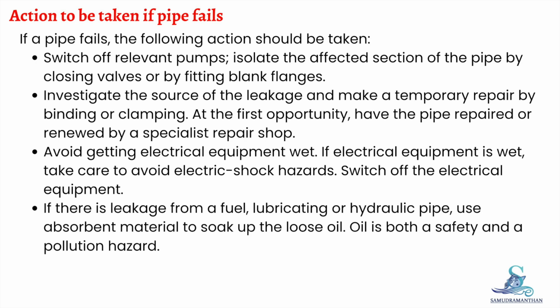Temporary repairs can be carried out by binding or clamping, but at the first available opportunity, the pipe should be properly repaired or renewed by a specialist repair shop. Care must be taken to avoid wetting electrical equipment. If electrical equipment becomes wet, there is a serious risk of electric shock. In such cases, the equipment should be switched off immediately and appropriate safety precautions taken.